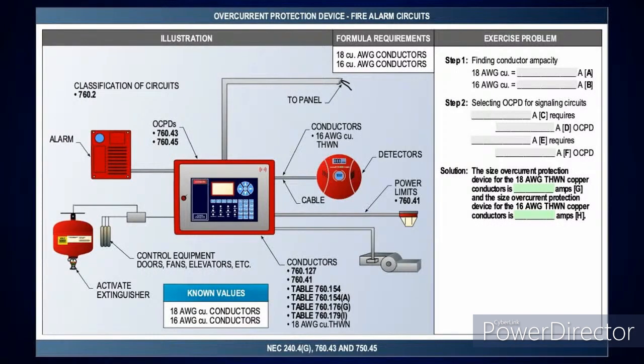This is actually a pretty cool illustration because they actually drew the new equipment and everything, and what you would see, the activated extinguishers, the alarm, the detectors and everything like you would see out in the field. And we're going to have you do here a number 18, number 16. You're going to do the exact same thing. You're going to go look at table 310.16 and get the amperage there, not size it, and then size your overcurrent protection device for those signaling circuits.